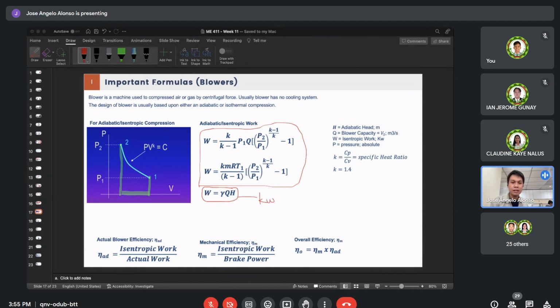Lastly, determining the efficiency of our blower. We have only two efficiencies here. The mechanical efficiency, which is the isentropic work divided by the brake power — this is just the blower efficiency, and the term is mechanical efficiency. The isentropic work can be obtained from the adiabatic or isentropic work equation, or from our general equation: specific weight multiplied by volume capacity and total head. Divide that by the brake power to get the mechanical efficiency, or blower efficiency.